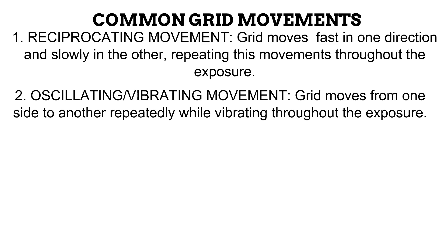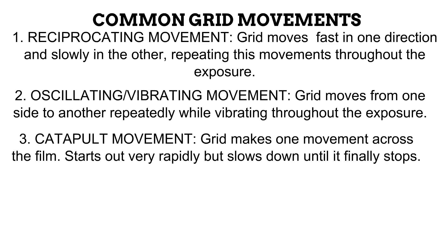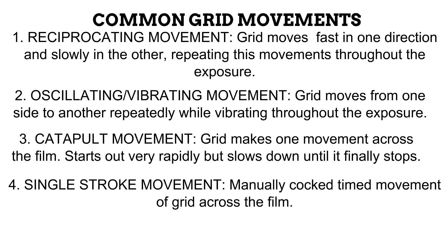Next is the catapult movement. Unlike the first two, the catapult movement makes just one movement across the film, starting out very fast but slowing down until it stops at the end of the exposure. Last is the single stroke movement, where the radiographer manually causes this movement by pulling a cock lever on the device before the exposure. It is, however, the less common movement today.